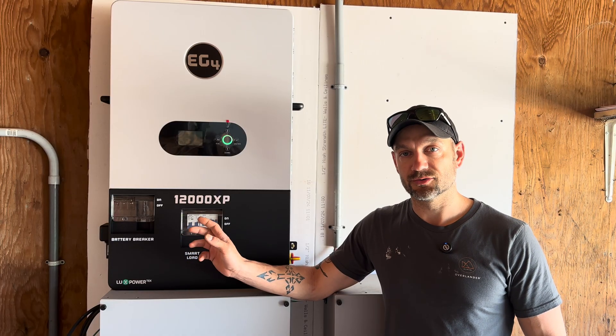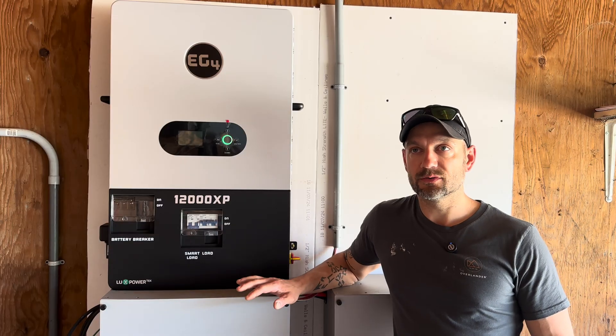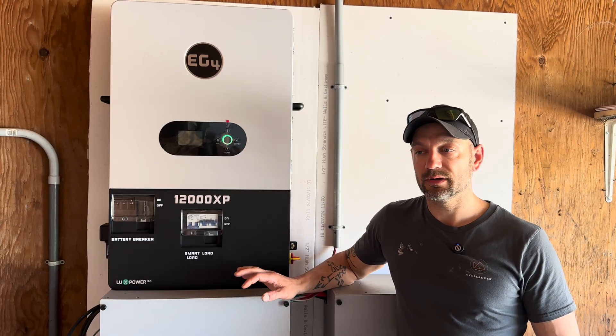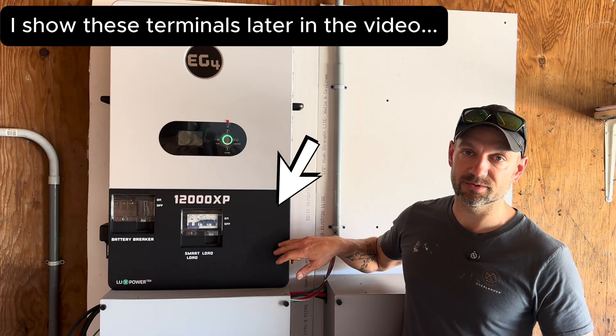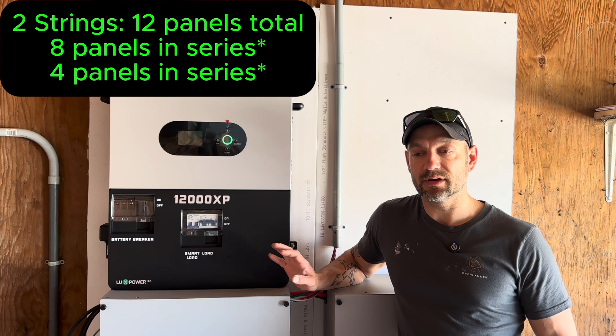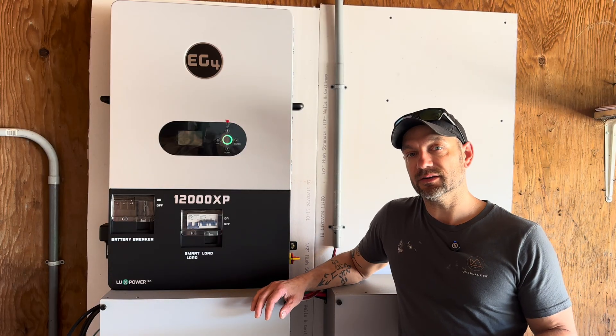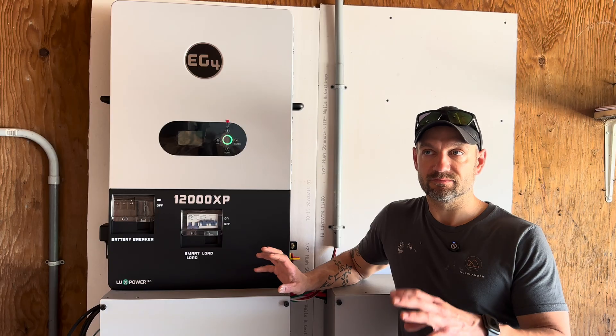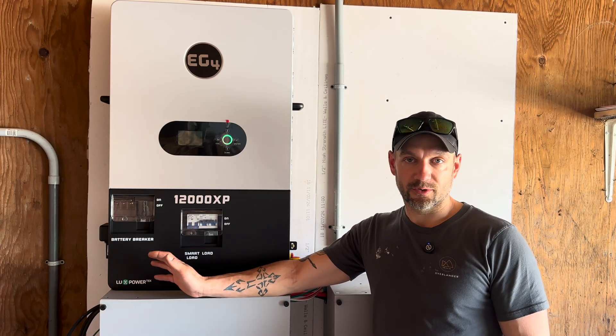On the solar side there are two MPPT controllers, each rated at 35 amps and up to 480 volts. There are two sets of terminals for each MPPT, so four sets total for four strings of solar. Right now I have two strings — a string of 8 panels and a string of 4 panels — each on their own MPPT because they're different sizes. That way each MPPT can get the most out of each string independently.